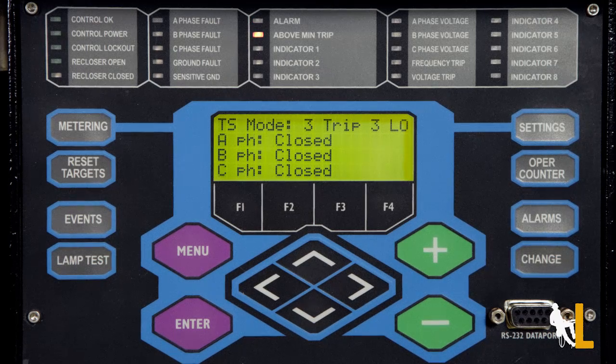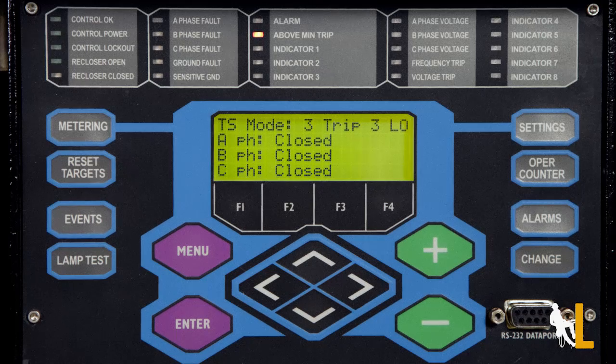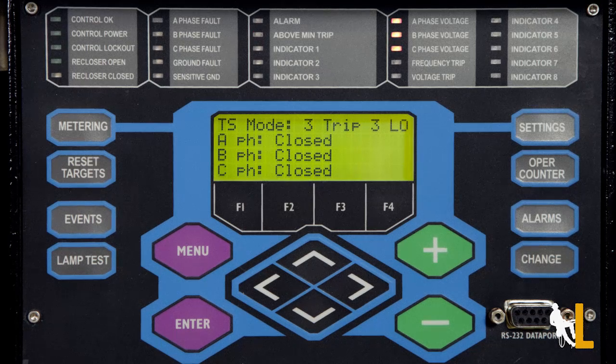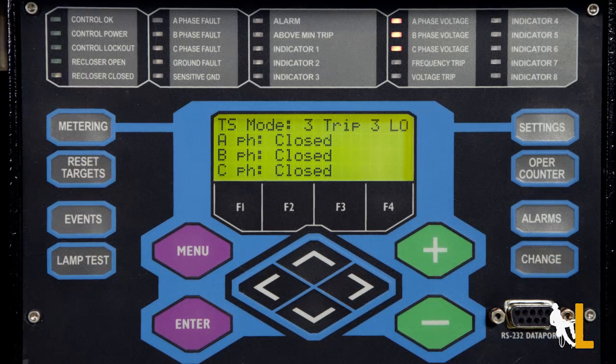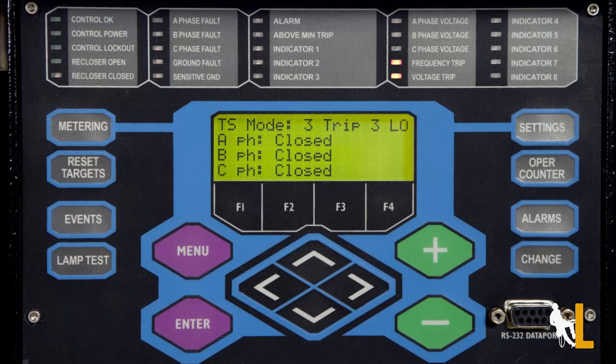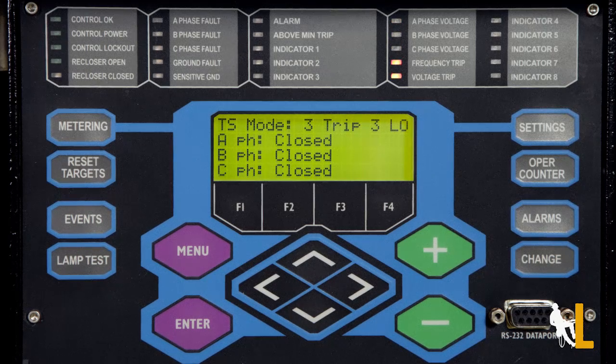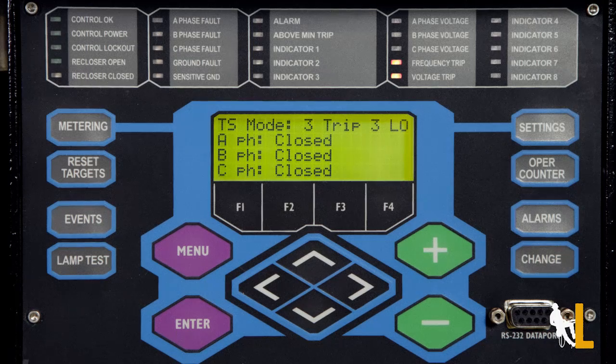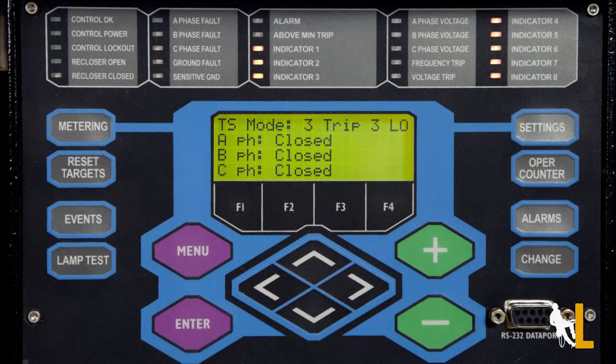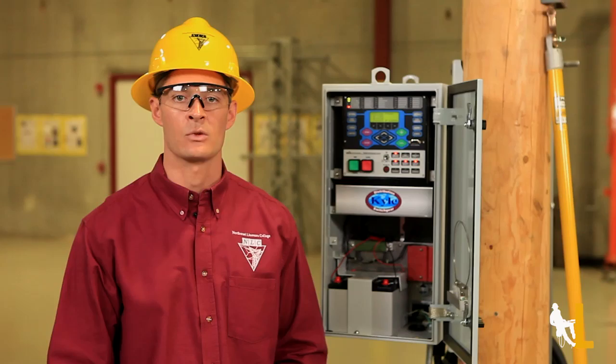Above minimum trip means that the current exceeds the level set for minimum trip. The phase voltage lights come on to indicate there is voltage on each phase. Voltage and frequency trip come on if the recloser trip due to high or low voltage or frequency. And finally, the indicator lights can be customized to come on in predetermined situations.